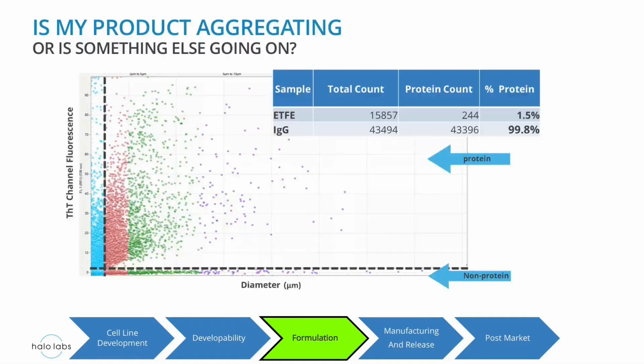But in addition to this, the Aura system has the ability to distinguish protein particles from other particles. The protein aggregates, compared to these protein plastic mimics, look the same under standard microscopic techniques, but using fluorescence membrane microscopy, we can easily distinguish the two and tell you which percentage of the population is proteinaceous versus not. And we do this in high throughput, measuring every single particle across the entirety of the sample.